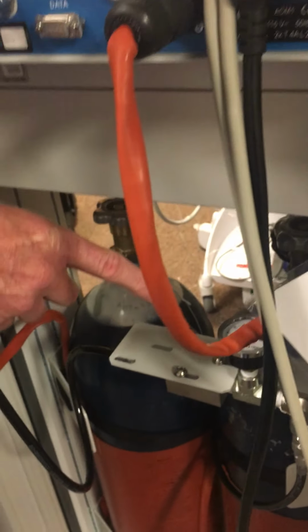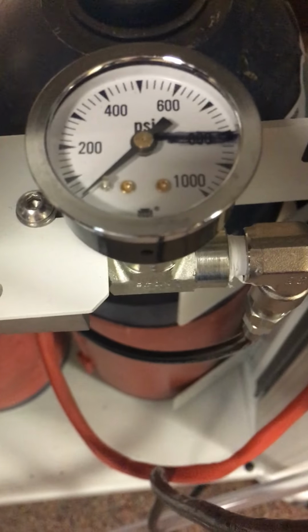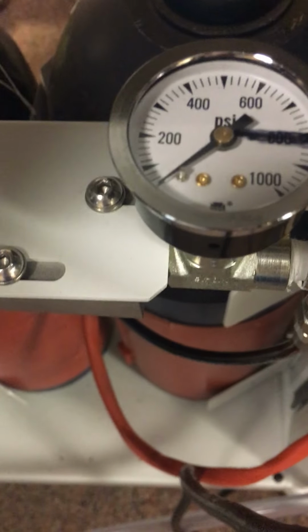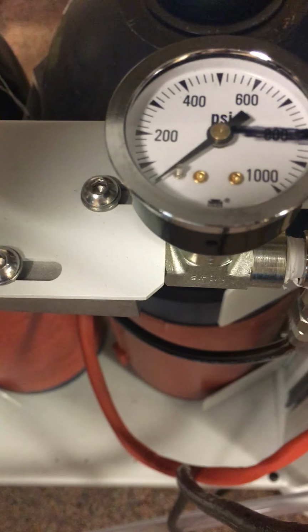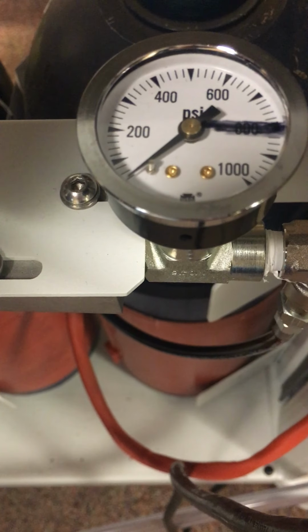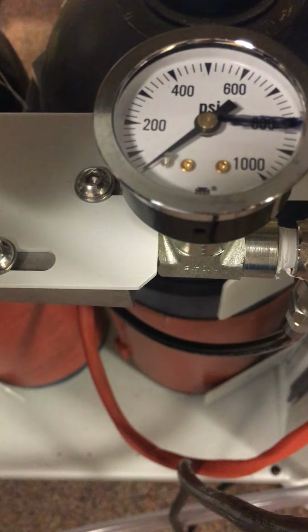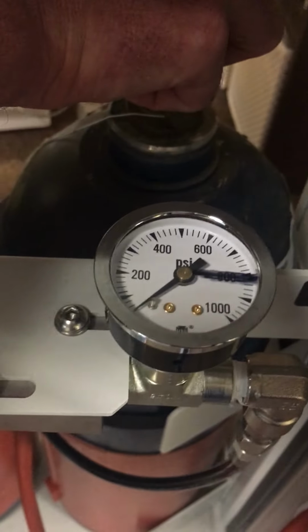If we come down here, we want to look at our pressure gauge, which is one of the most important pieces of this machine. There's a line that's marked there for 800. If we're at 800, we have enough nitrous to get through a case. At this point, we want to go ahead and turn our machine on. The machine's on.